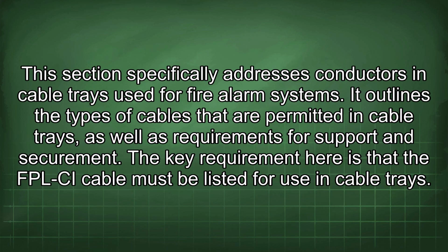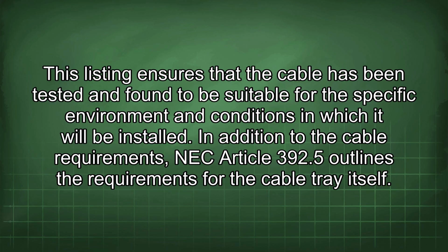760.179. This section specifically addresses conductors in cable trays used for fire alarm systems. It outlines the types of cables that are permitted in cable trays, as well as requirements for support and securement. The key requirement here is that the FPL-CI cable must be listed for use in cable trays. This listing ensures that the cable has been tested and found to be suitable for the specific environment and conditions in which it will be installed.